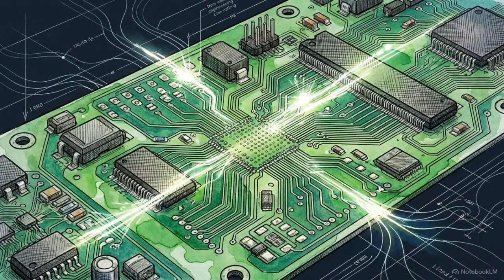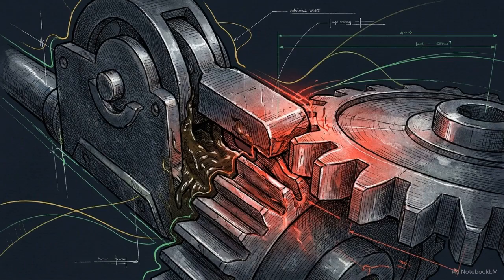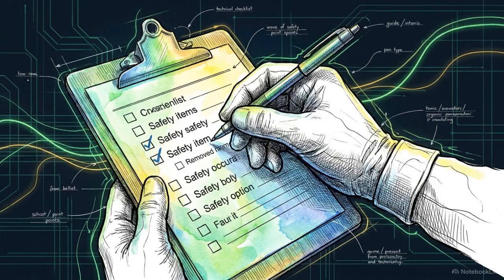The ATS controller executes its logic rapidly, but that logic is a digital abstraction. The controller issues commands, but it is blind to the physical realities of jammed mechanisms or welded contacts inside the switchgear. Because of this blindness, human operators follow a strict 5-step protocol: authorize, verify, operate, confirm, and record.